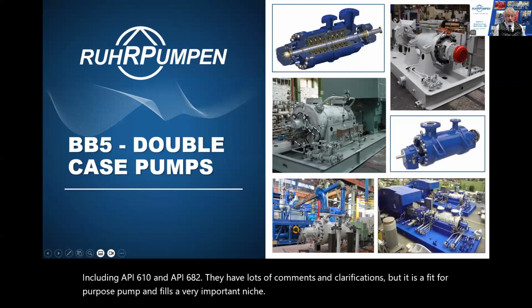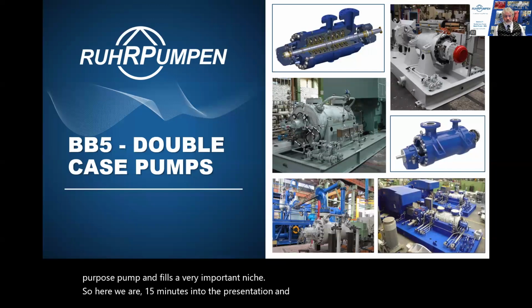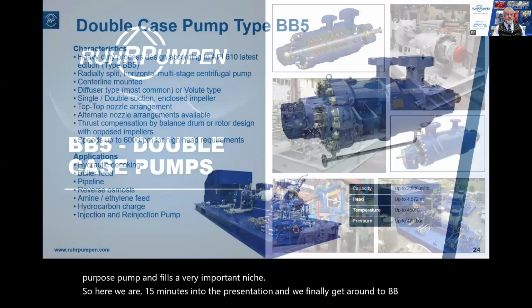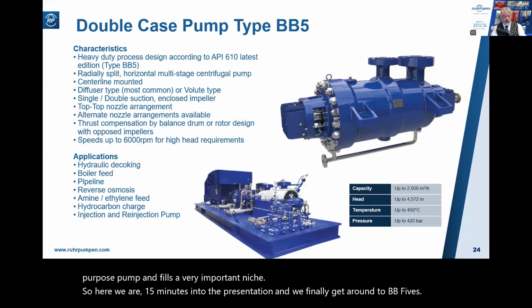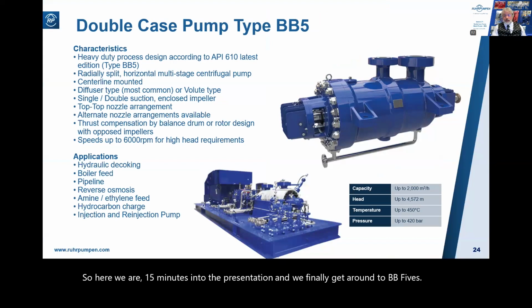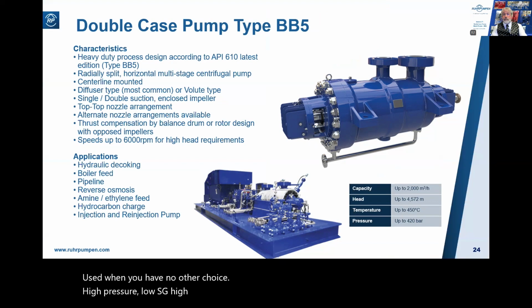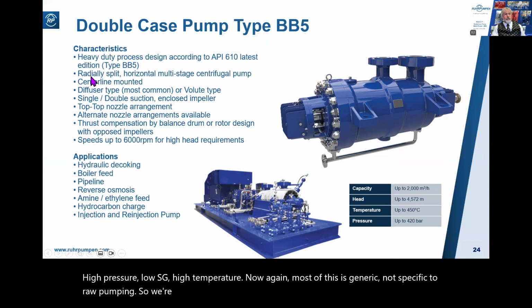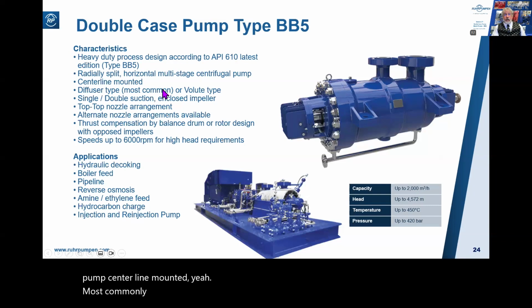So here we are, 15 minutes into the presentation, and we finally get around to BB5s. Used when you have no other choice. High pressure, low SG, high temperature. Now again, most of this is generic, not specific to Ruhrpumpen. So we're talking here about a radially split, horizontal, multi-stage centrifugal pump. It's centerline mounted. Most commonly, it's a diffuser type, but some manufacturers have a volute type, and we'll look at both.